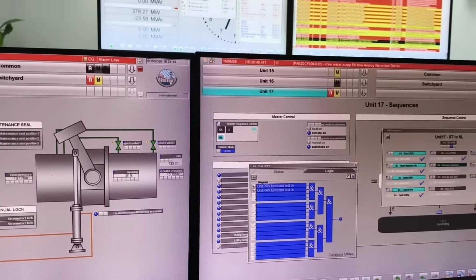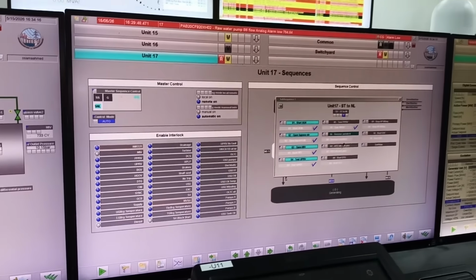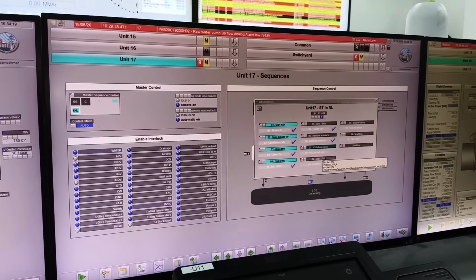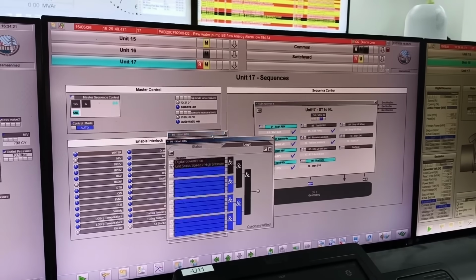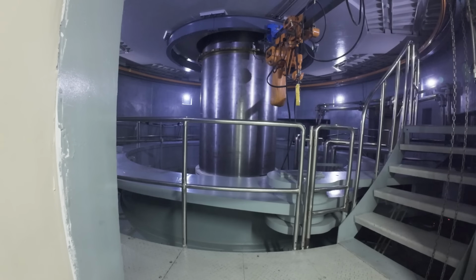Okay, step number 7 and step number 8 is governor activation and turbine acceleration. The hydraulic governor provides the physical force needed to move the wicket gate. Meanwhile, the digital turbine governor, or DTG, acts as the brain of the entire speed control system. Together, they constantly regulate turbine speed. In simple terms, if electric load changes, the turbine speed tries to change with it. The governor detects that instantly and adjusts the wicket gate opening to stabilize rotational speed.